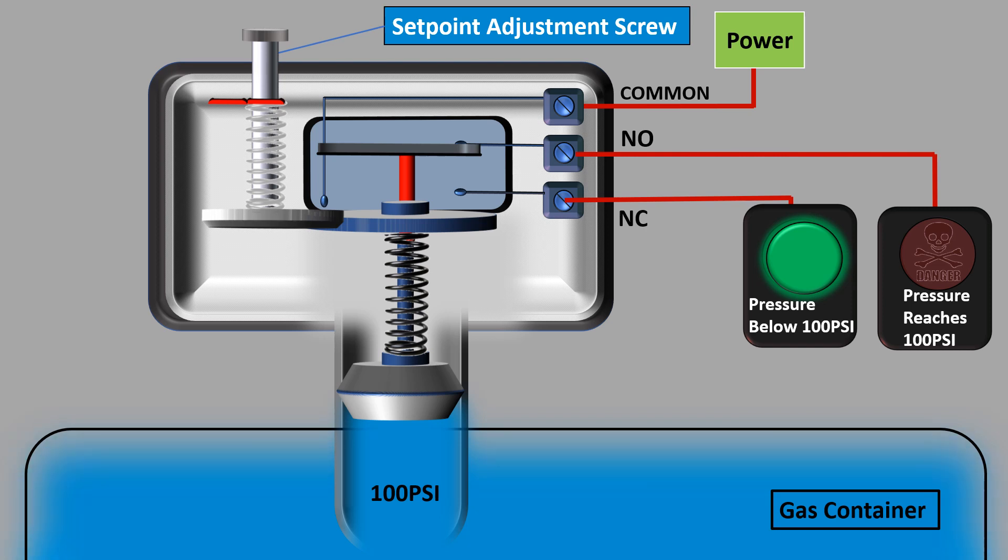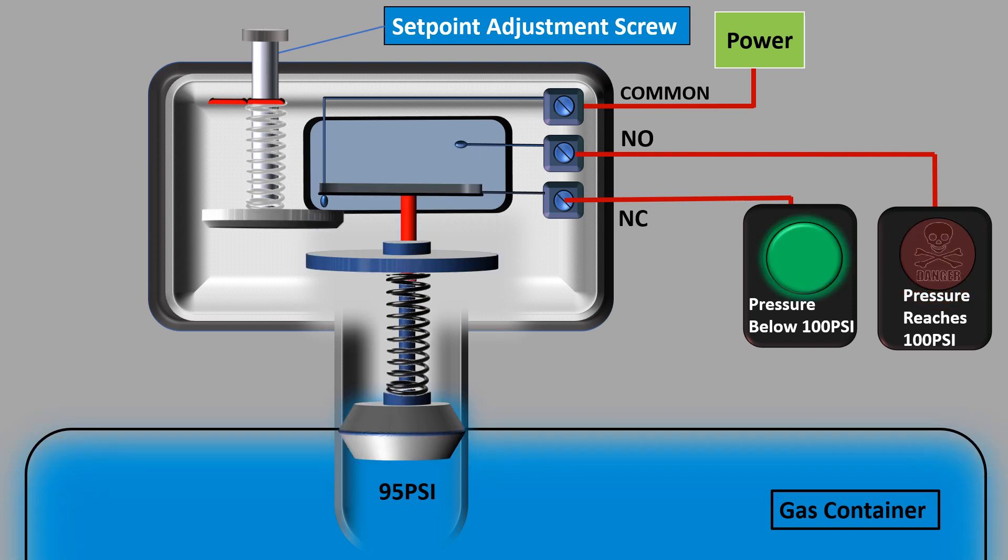Now the normally open contact will get power and the red light glows while the green light switches off. If this pressure switch has a differential of 5 psi, then reset pressure will be 95 psi, which means that when the pressure reduces to 95 psi, then the switch will come back to its normal state—that is, green light will be on and the red light will be switched off.